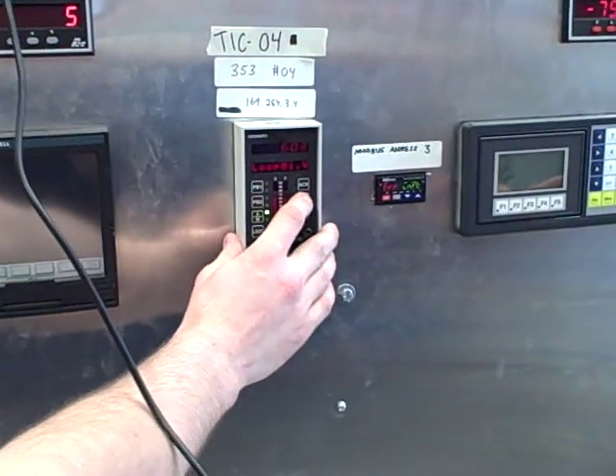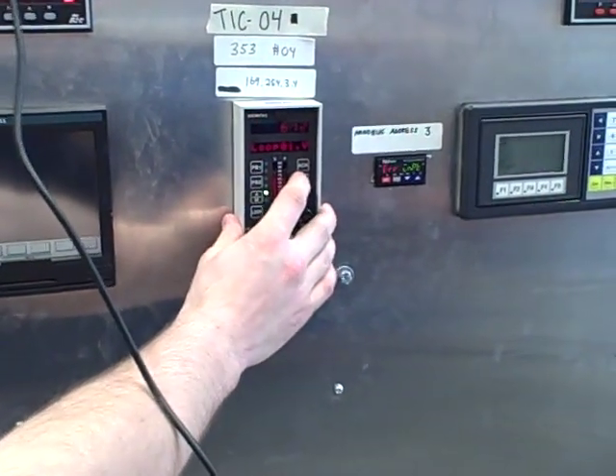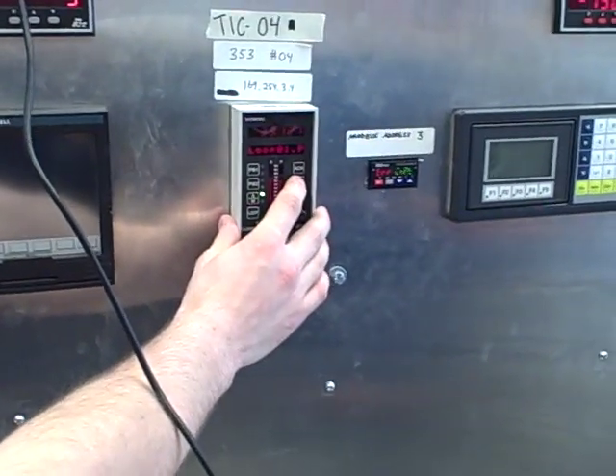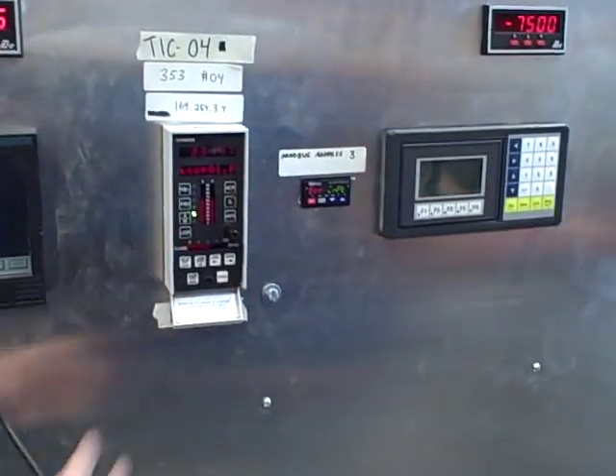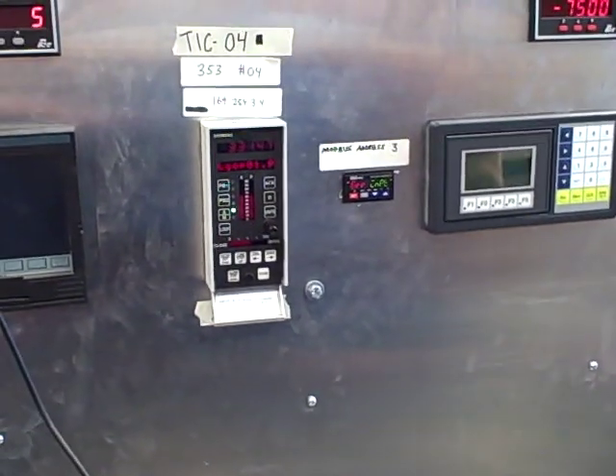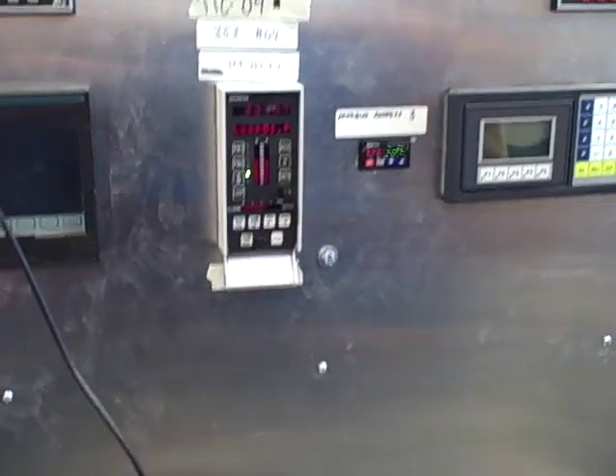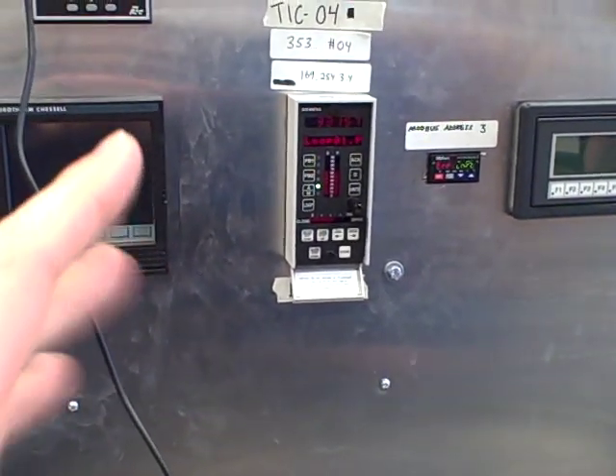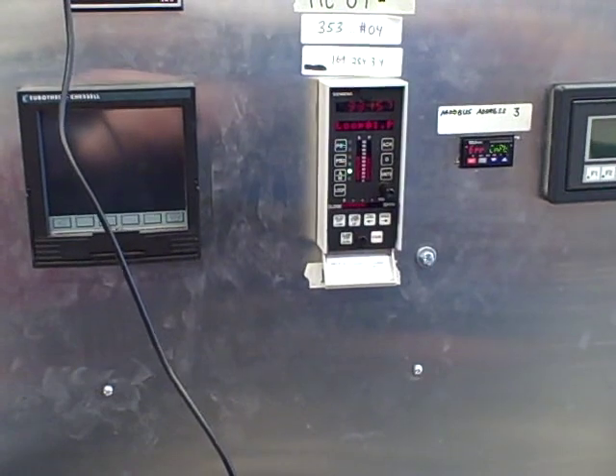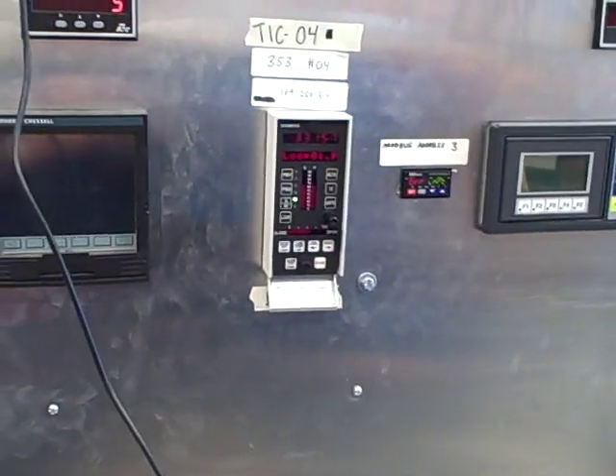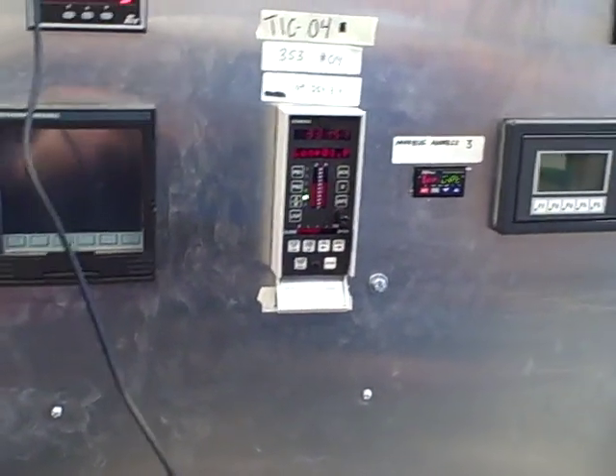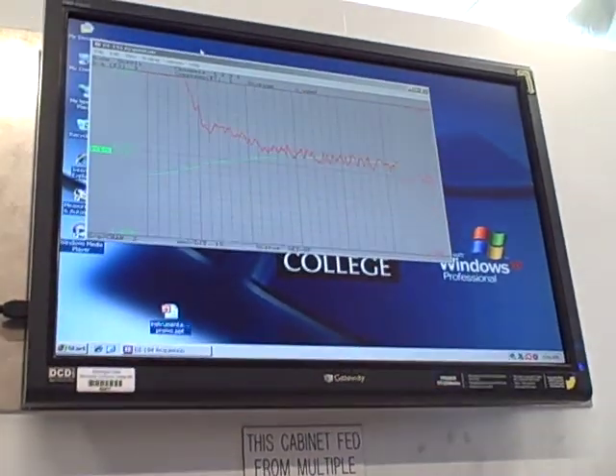So that's in percent. And that's going to convert into your percent duty cycle of that power. So if you're on for about sixty percent of the time and off for about forty percent, that turns into a PWM signal pulsing power to the heating element. And we're trending it there doing our tuning.